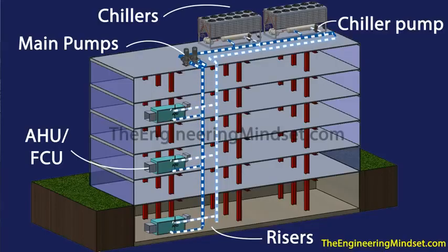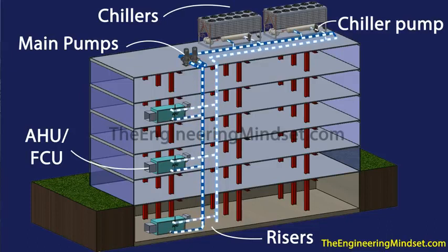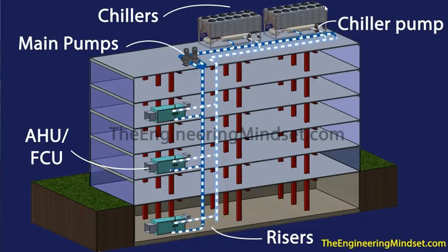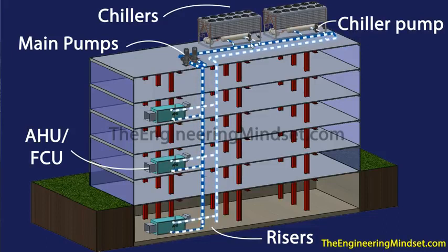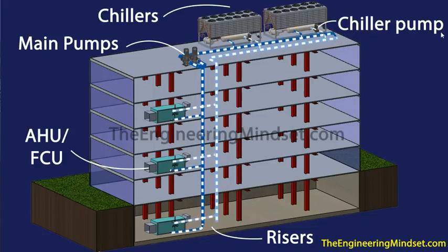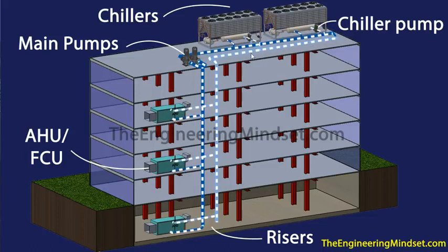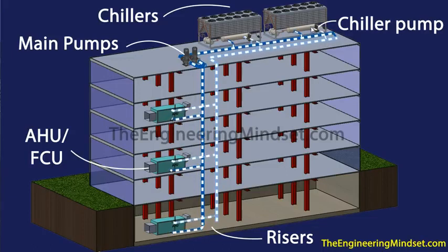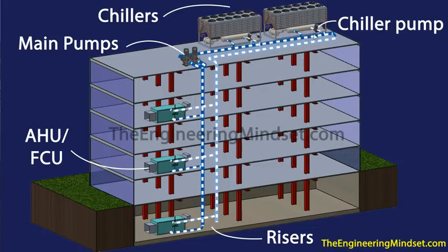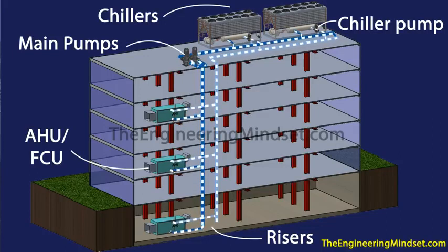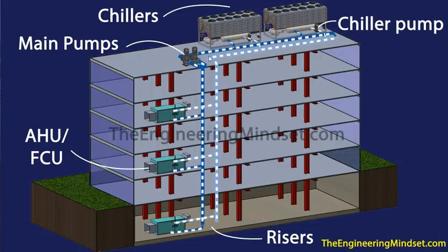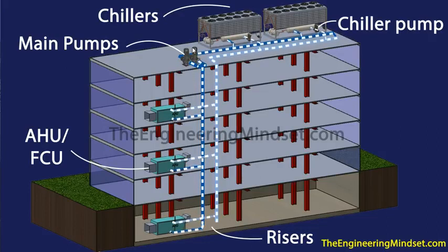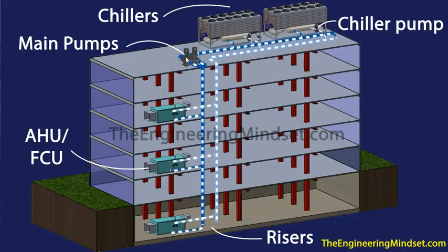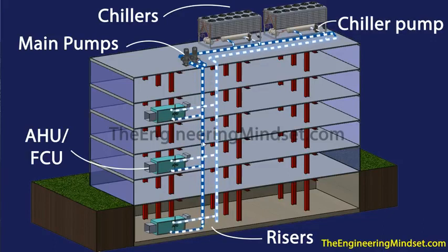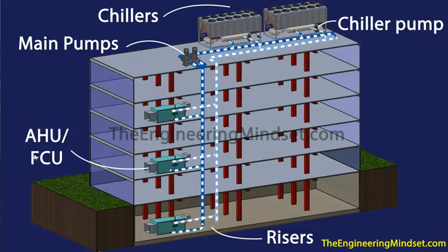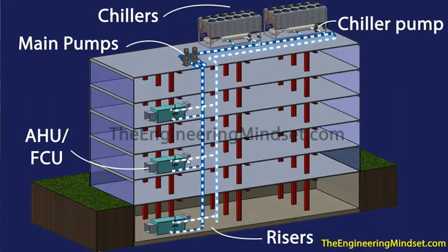So first of all, we've got a simplified 3D schematic of a typical air-cooled chiller system. You can see we've got the two air-cooled chillers up on the roof, and they've both got small chiller pumps on there, circulation pumps, so they'll pull return water in and push that through the evaporator and then push that cooler water back out into these headers. These will run along and then enter into the main pumps over here. The main pumps will then push that water, usually one of them will run at a time, there might be duty standby, and that will then push that chilled water around the building to wherever it's needed, off into the AHU, the fan coil units, etc., around the building.